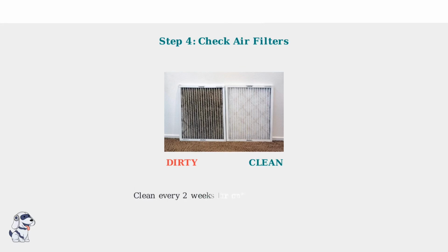Dirty air filters are a common cause of poor cooling. Compare your filter to these examples. Clean or replace filters every 2 weeks for optimal performance. Blocked filters restrict airflow and reduce cooling efficiency significantly.